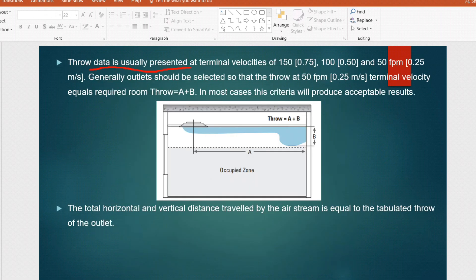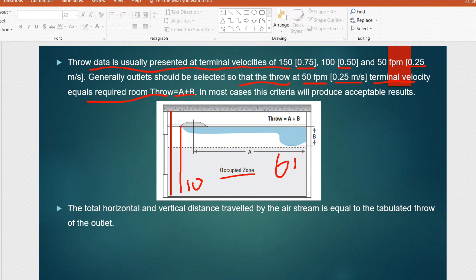Normally, throw data is presented at terminal velocities of 150 ft/min (0.75 m/s), 100 ft/min (0.5 m/s), and 50 ft/min (0.25 m/s). Generally, outlets should be selected so that the throw at 50 ft/min (0.25 m/s) terminal velocity equals the required room throw, which is A plus B. For example, if the total height is 10 feet and the occupied zone is 6 feet, then B equals 4 feet. If the horizontal throw distance A is 7 feet, total throw distance is 11 feet — selected at the 0.25 m/s terminal velocity.